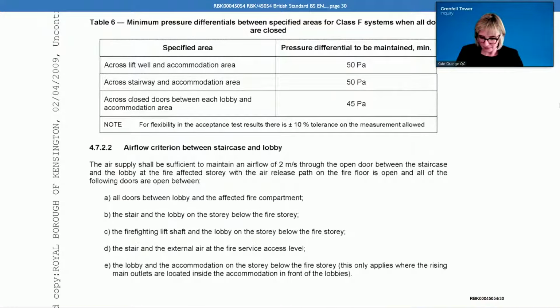Yes, I was. Were you also aware that BS 12101 made clear that if different pressurised or depressurised zones are connected to the same fan or set of fans by a common system of ductwork or shafts, smoke control dampers needed to be used? Were you aware of that? Yeah, but we were using the SCA guide on the job. The element of the 12101 Part 6 was, in fact, the testing regime, the 2 minutes, which was taken for that guide and used as a criteria for the SCA. So I would have been looking in the SCA guide, their criteria for smoke control dampers.